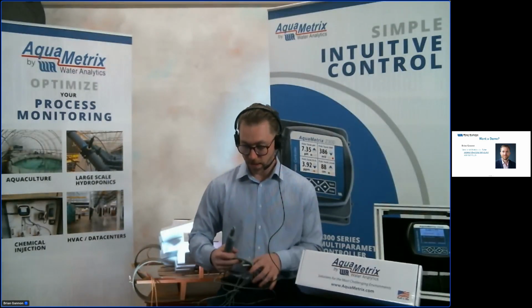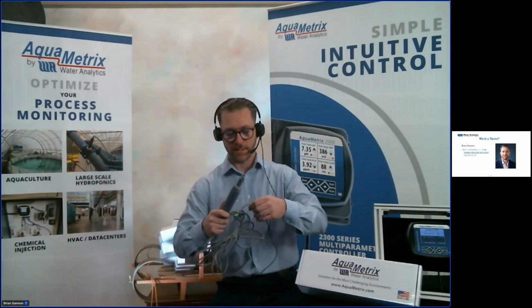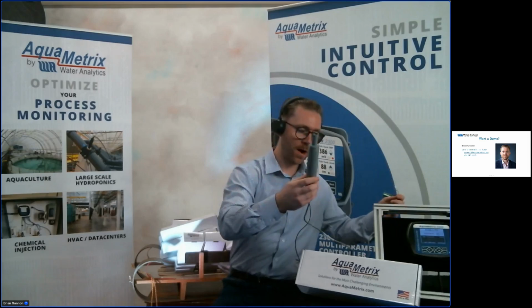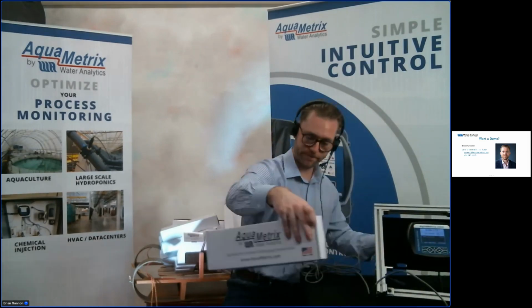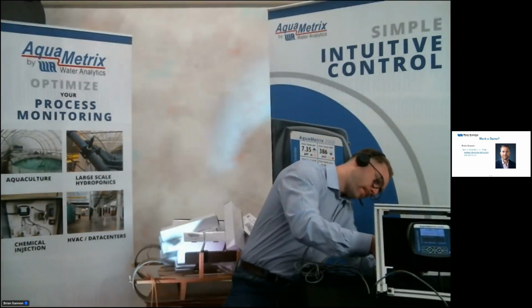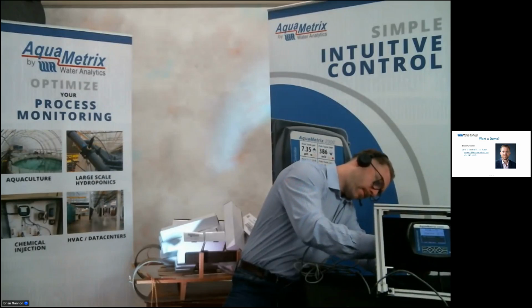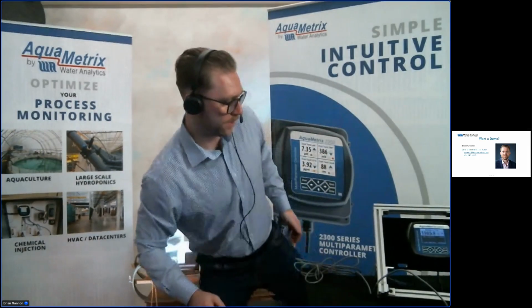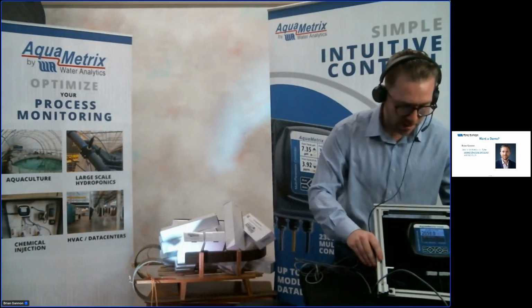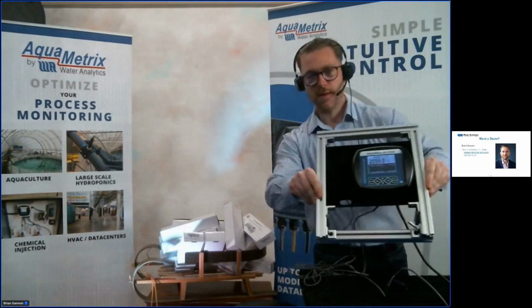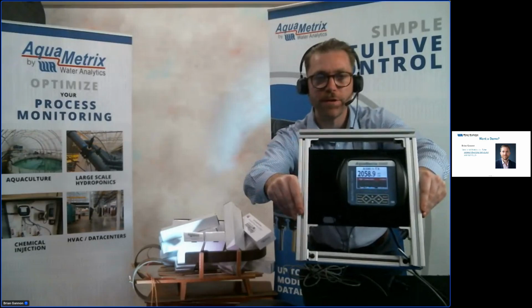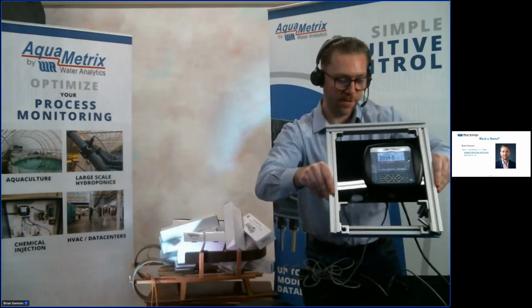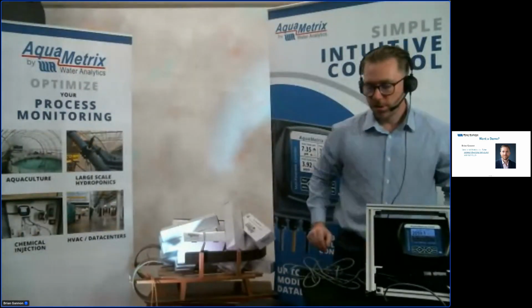The scaling on this sensor, a cell constant 1 ASM1TX, runs from 4 milliamps at 0 to 20 milliamps at 2000 microsiemens. It's as simple as connecting the two wires and putting it into the solution. Plug the sensor in, and you can see we're reading right around 2000 microsiemens here. This is definitely tap water you wouldn't want to drink, but I threw a little salt in there to get the readings a bit higher.